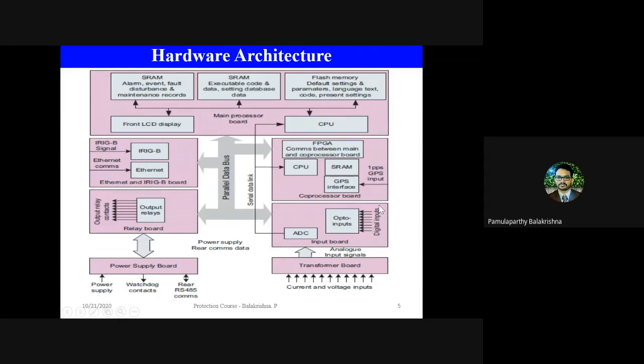Okay. So apart from digital inputs and analog inputs, which are required to know the status and condition of different equipment, there are also the output relays. Again, output relays can be digital output relays as well as analog output relays. Digital output relays are used to control any component of the power system. Like if you want to trip the breaker from on to off, you send it as a digital output command. If you want to control any capacitor bank, all those things are sent as digital output commands.